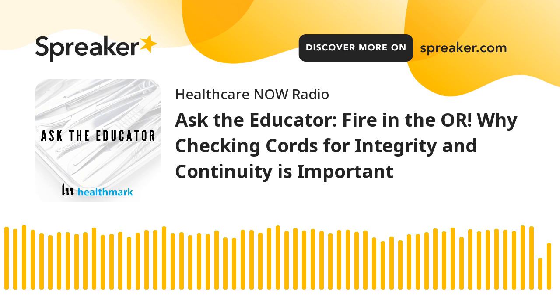That should get people's attention right away — surgical fires and burns to the patient are serious things that sterile processing really needs to care about. Typically when we talk about insulation testing, most people think laparoscopics, but that's not the only thing you should be testing. If we look at the amendment to ST-79, it does say cords — not only insulation testing of cords, but conductivity. We need to make sure the cords are actually working the way they're supposed to work. Jahan, can you give us some examples of things that have happened from damaged cords?